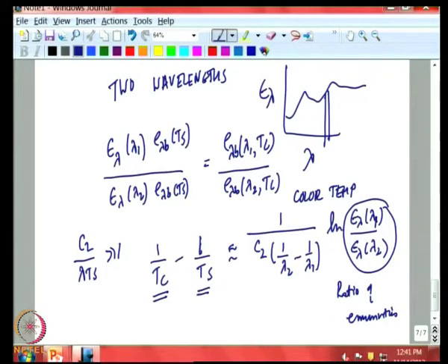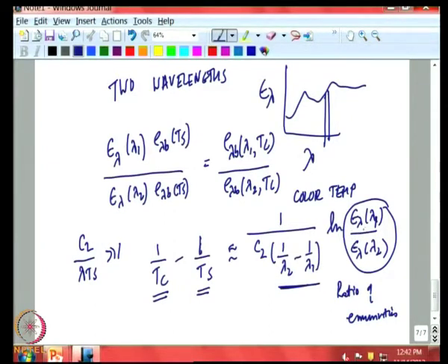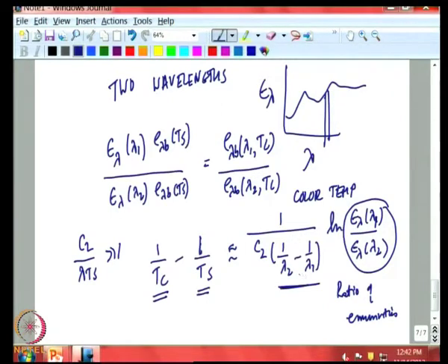So the accuracy of measurement now depends not on the value of emissivity, but on ensuring that emissivity does not vary very much with wavelength. However, there is a challenge: you would like the two adjacent wavelengths to be quite close, but if they are too close, the factor (1/λ_2 − 1/λ_1) goes to 0. This demands that the two wavelengths should not be too close. But at the same time they cannot be too far, because if they are too far, the emissivity ratio may depart significantly from 1. So there is a trade-off in the choice of wavelengths.